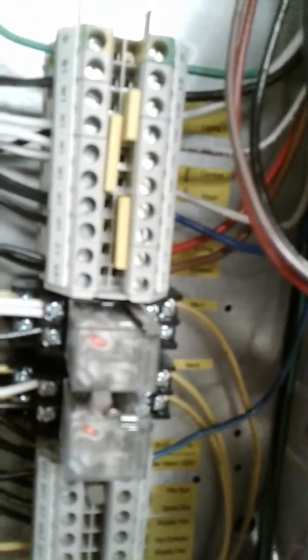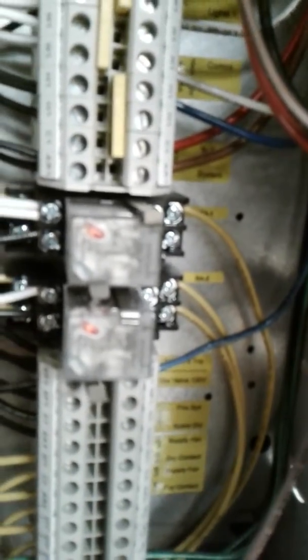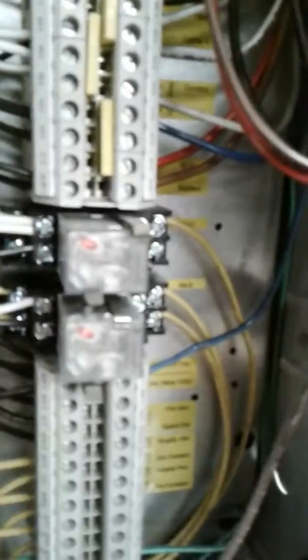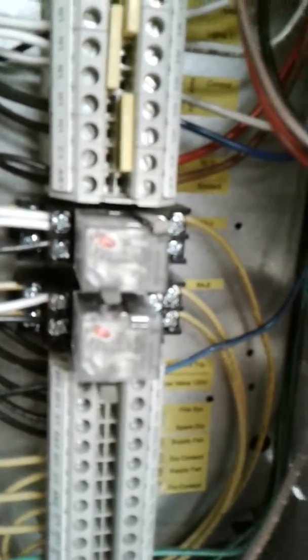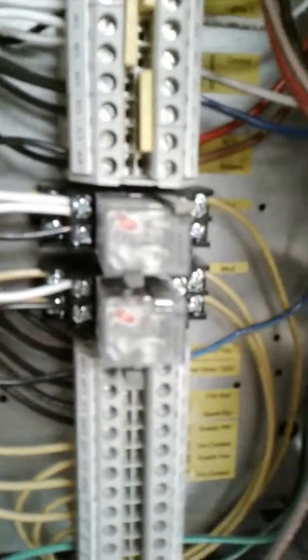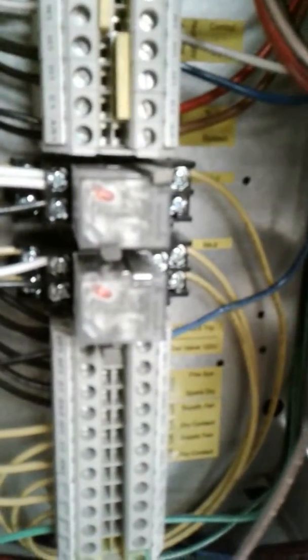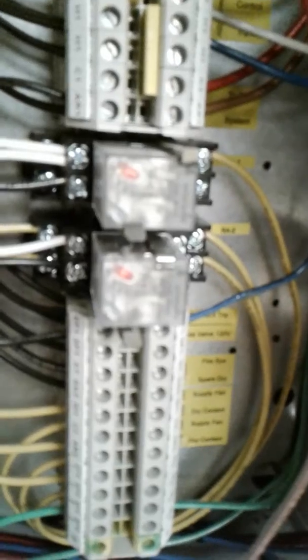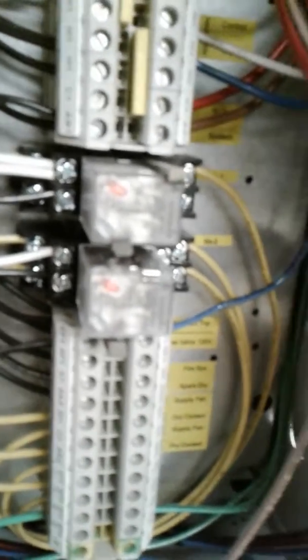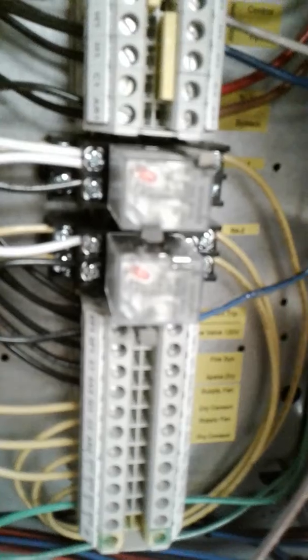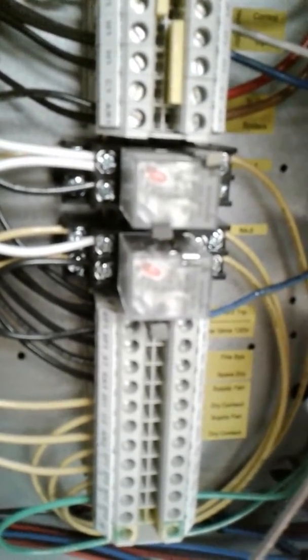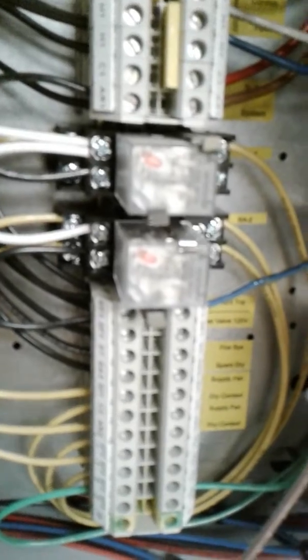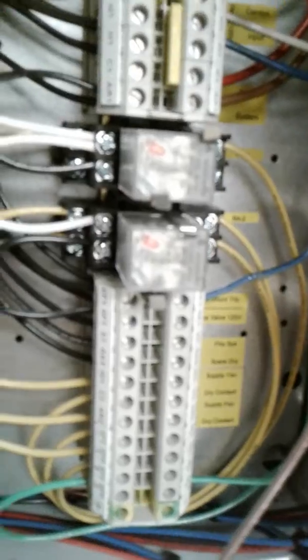But, with these, with the C1 and the AR1, it's actually supplying power. And the whole time this machine is on, you want it to be making contact at the micro-switches so that there is power going between these two contacts right here. And it goes through the micro-switches of every ANSUL system and comes back here so that every single one of them will know what's going on. And every single one of them will turn on its exhaust fan and turn off its make-up air unit. And then, it's pretty much cut and dried.